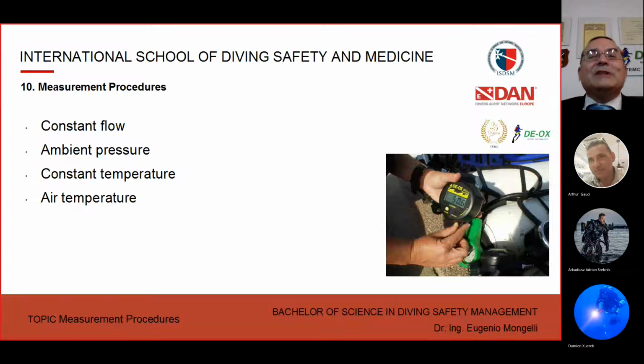was hot, it was under the sun. So the gas temperature that went into the cylinder, even if the cylinder was at a standard temperature, in the shade, not under the sun, was a higher difference. So when they put the hot pure oxygen together with the air coming from the compressor at ambient temperature, the mix didn't happen well. There was a stratification of the temperature, and the gas didn't mix.